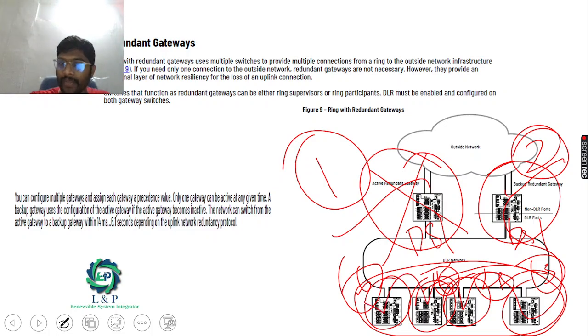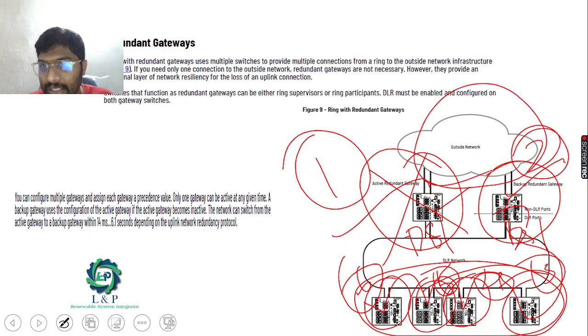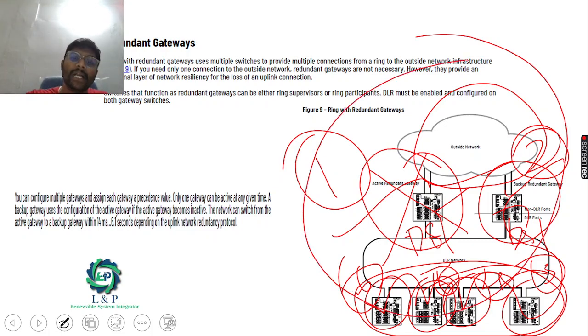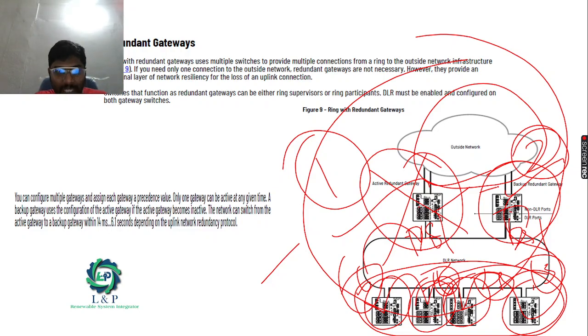Okay, and both the devices have the capability to connect with the outside network devices using different VLAN IDs. But before making any sort of physical connection, try to configure each and every device separately and then make the physical connections. Most importantly, the switchover time will be from 14 milliseconds to 6.1 seconds. Whenever a network fails, the redundant network takes 14 milliseconds to 6.1 seconds.